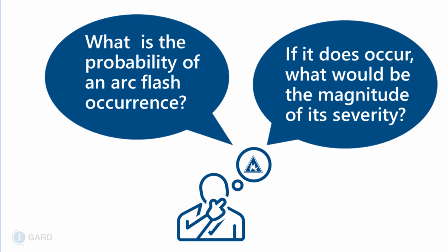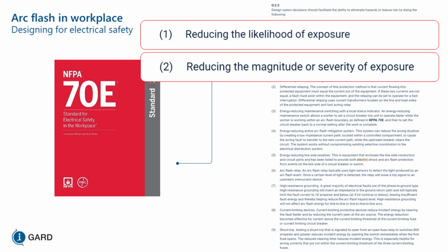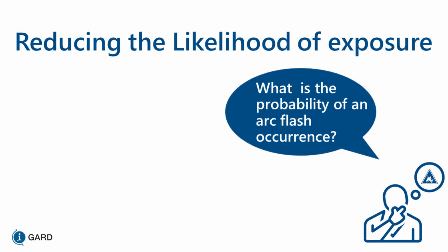So what is the probability of an arc flash occurrence? And if it does occur, what would be the magnitude of its severity? NFPA 70E again is throwing you to reduce the likelihood of exposure. If you look at Annex O 2.2, the owner and designers have to reduce the likelihood of exposure and reduce the magnitude of exposure. There are very few things you can do to reduce the likelihood of exposure. One of them is not to work on it at all, but you have to assume everything is energized until you prove it to be de-energized. So working on it energized is energized work.